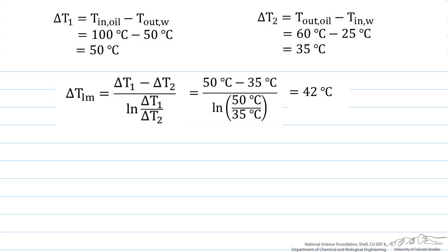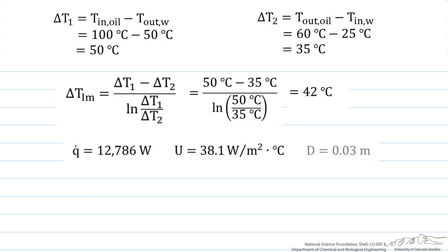And now let's put in numbers for our length. For sizing a heat exchanger using parallel flow, we found that our heat transfer rate was 12,786 watts, our overall heat transfer coefficient was 38.1 watts per meter squared degrees C, our diameter was equal to 0.03 meters, and our delta T log mean is 42 degrees C.